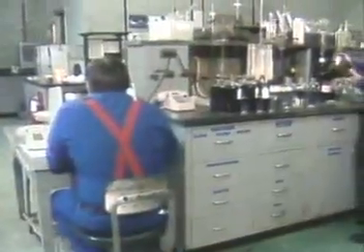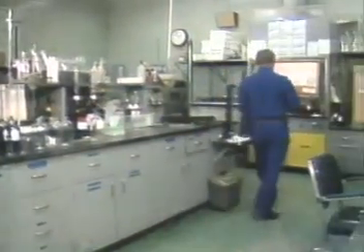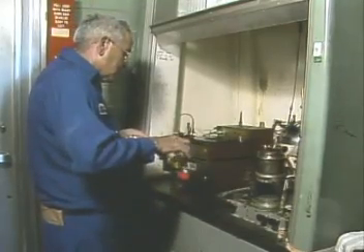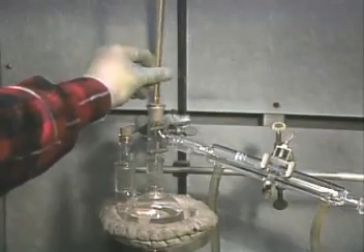Indirect composition measurements are analyses in which one measured property is used as an indicator of another property. In other words, the measurement of a property is used to determine product composition. One common indirect measurement is boiling temperature. For example, since the boiling points of the components in a feed mixture are known, the components in a product can be indirectly identified by their boiling points.